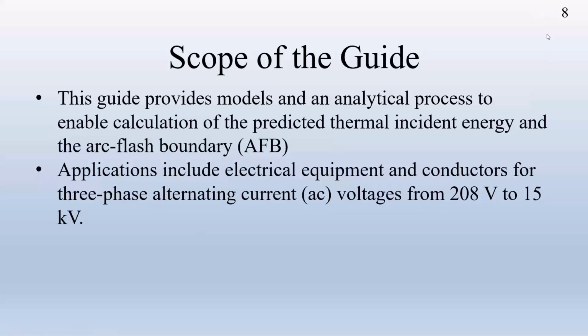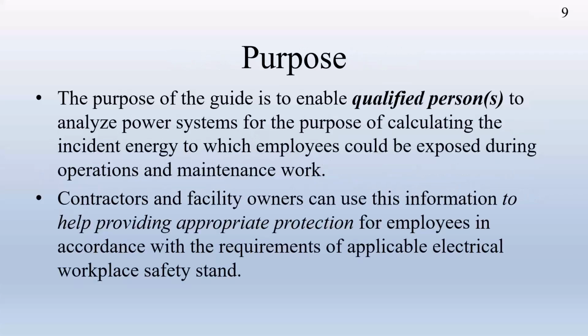In this guide, we provide the model in an analytical process to enable calculation of the predicted thermal incident energy, arc flash boundary, and the arcing current. Every model has a limitation. Here we cover 208 V to 15 kV, in three-phase AC systems. The purpose of this guide is to help a qualified person analyze the power system to calculate the IE that an employee could expect during operating or maintenance work if something happened. It also provides some information for the owner to help provide appropriate protection.